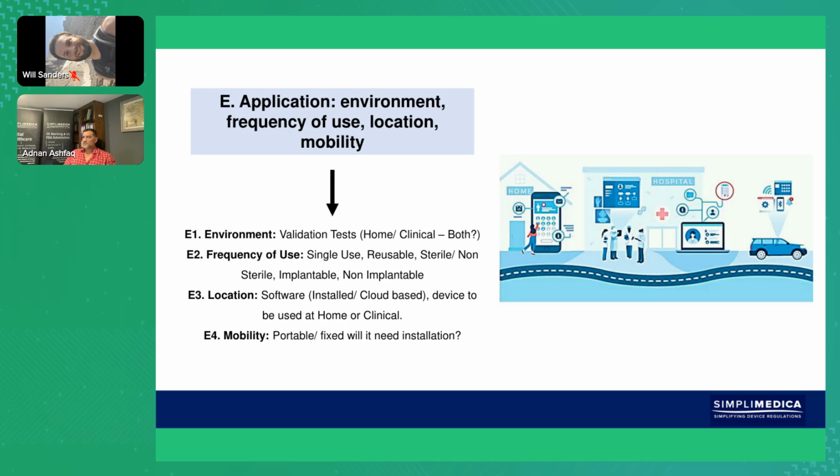It may be a cloud-based software, so there's no installation, or we could have said that it's non-sterile, but there may be some sterile components which you're buying in that you're not CE marking yourself, but the overall device then contains a sterile swab or a sterile component. So therefore, your quality management system also has to make sure that it's equipped for that intended purpose and intended use.